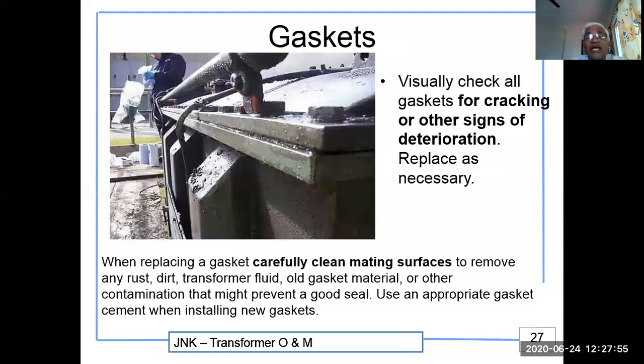Gaskets. Visually check all the gaskets for cracks or other signs of deterioration. Replace as necessary. When replacing a gasket, carefully clean the mating surface to remove any dust, dirt, transformer fluid, old gasket material, or other contamination that might prevent a good seal. Use an appropriate gasket cement when installing a new gasket. Once you have opened the top cover, the old gasket cannot be used. You have to put a new gasket. So before opening the top cover, please ensure that a new gasket is available with you. Holes are punched on that.